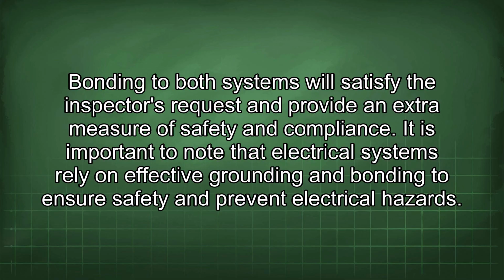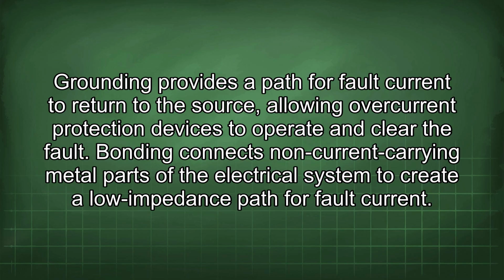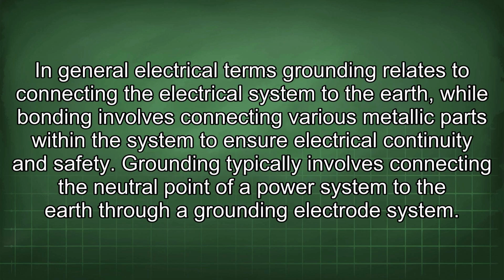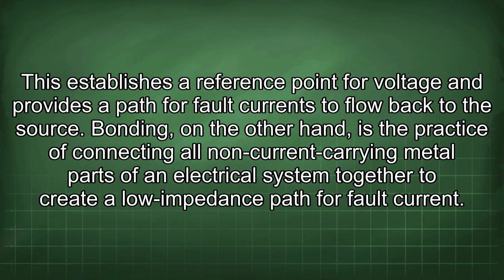It is important to note that electrical systems rely on effective grounding and bonding to ensure safety and prevent electrical hazards. Grounding provides a path for fault current to return to the source, allowing overcurrent protection devices to operate and clear the fault. Bonding connects non-current carrying metal parts of the electrical system to create a low impedance path for fault current. In general electrical terms, grounding relates to connecting the electrical system to the earth, while bonding involves connecting various metallic parts within the system to ensure electrical continuity and safety. Grounding typically involves connecting the neutral point of a power system to the earth through a grounding electrode system. This establishes a reference point for voltage and provides a path for fault currents to flow back to the source.